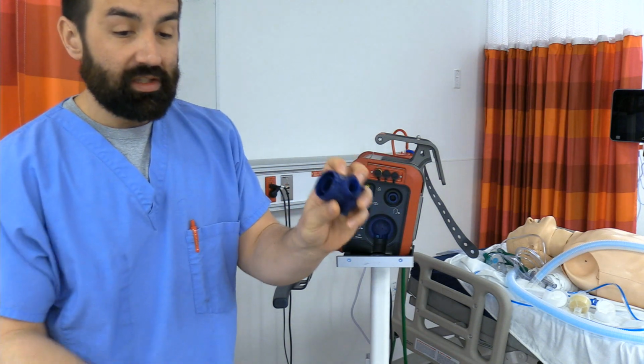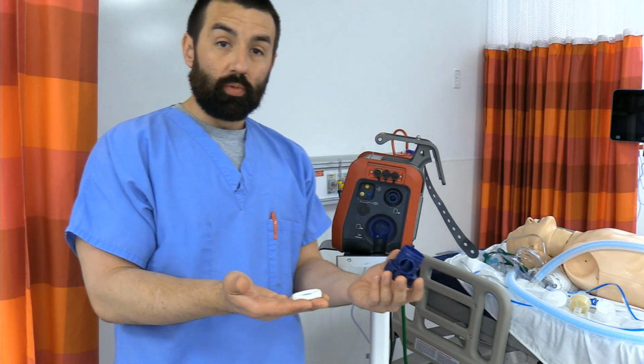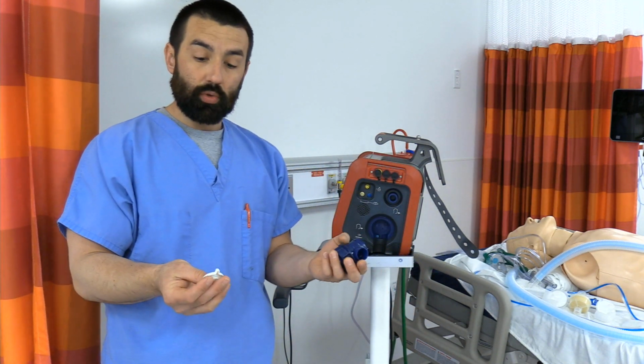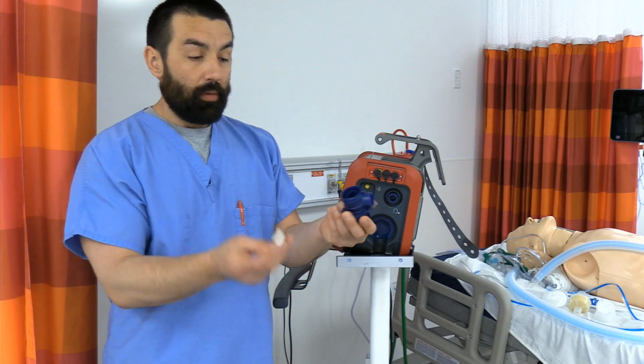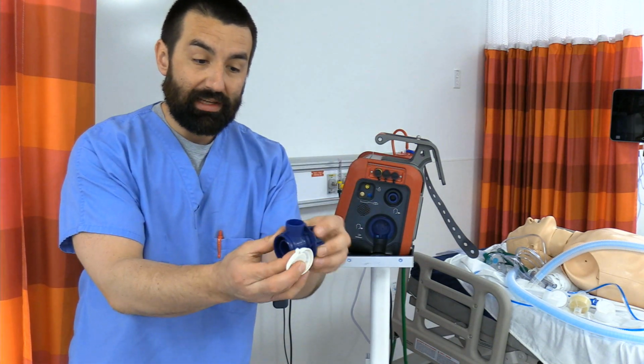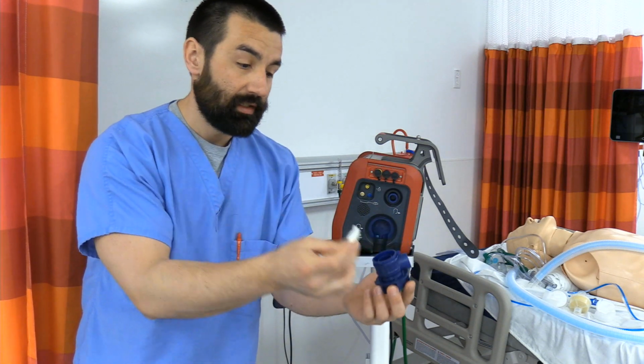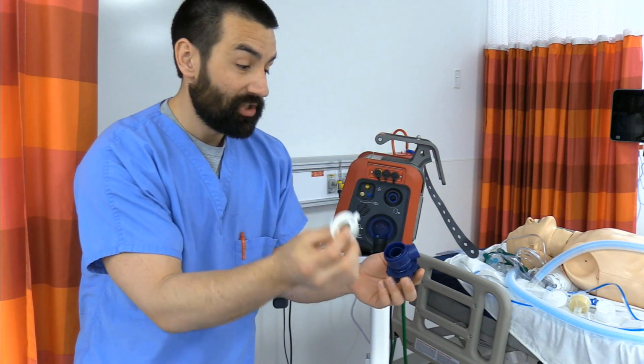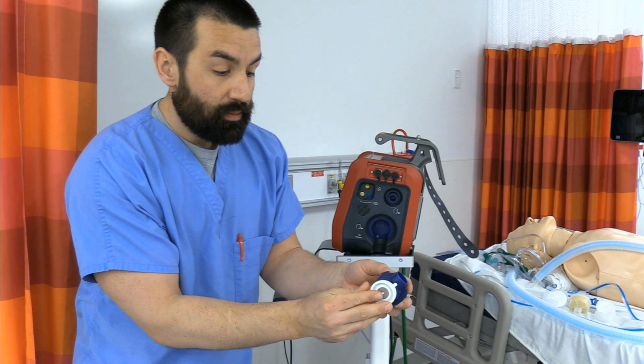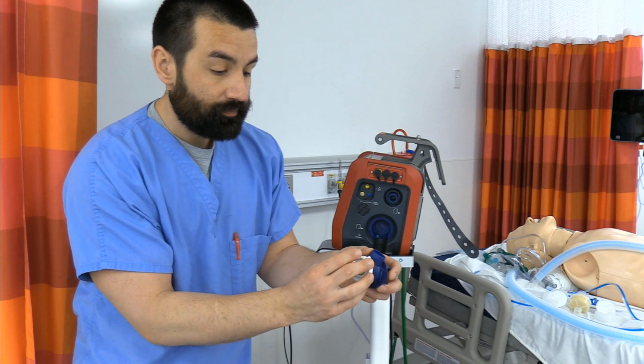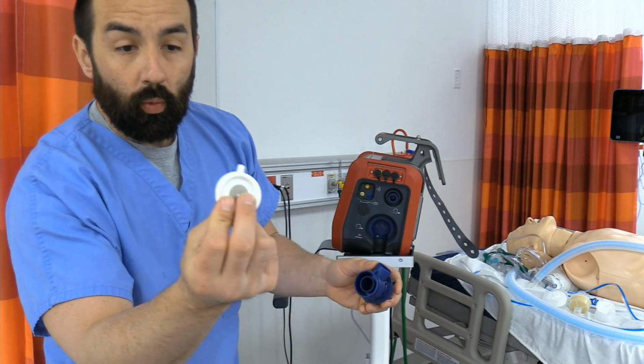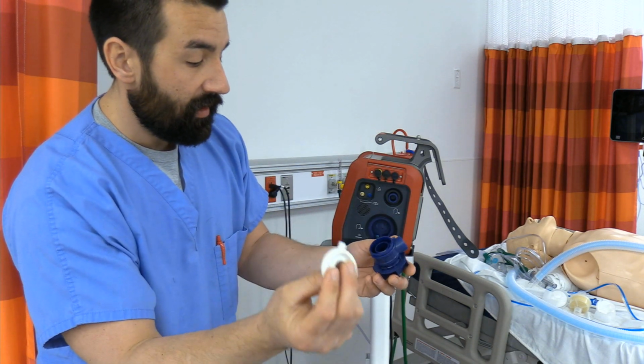So this particular piece I'm showing you here would be a reusable, meaning we'd have to sterilize it between patient use. Both parts of this, okay, so this is the plastic housing that's going to have this, which is very, very important, a weighted exhalation diaphragm. This piece seats on top of that.